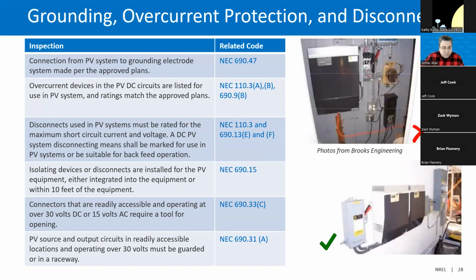And in this picture, the upper photo shows a DC disconnect next to an inverter, but the AC disconnects are outside, which is not okay. And the lower photo here shows AC and DC disconnects on the side of the inverter, which should be the proper way of installing the disconnects.